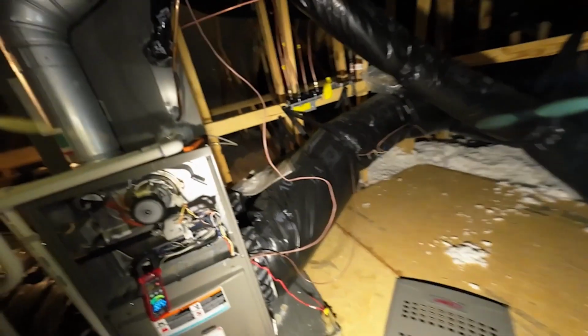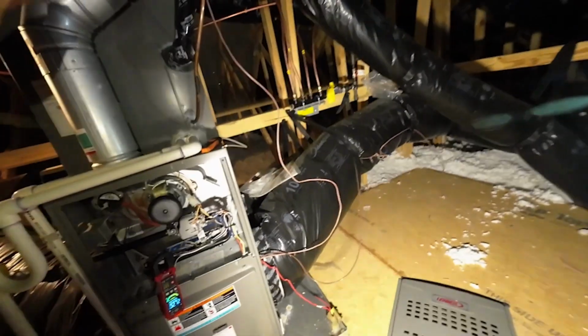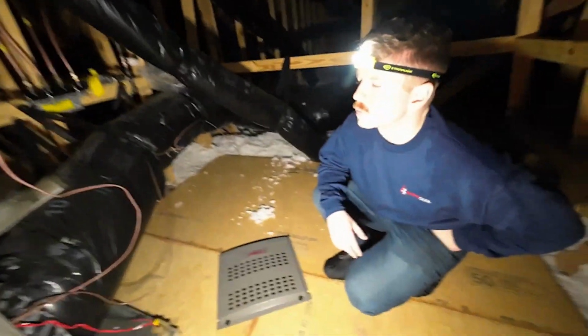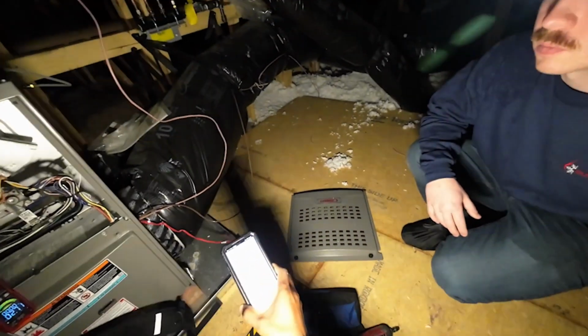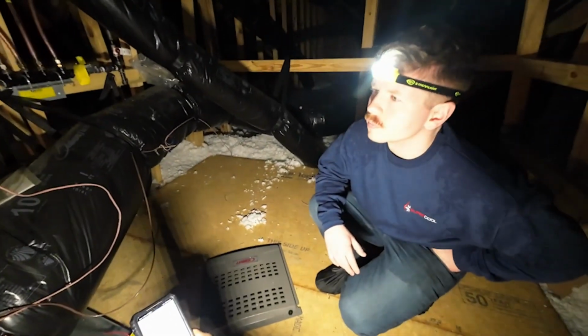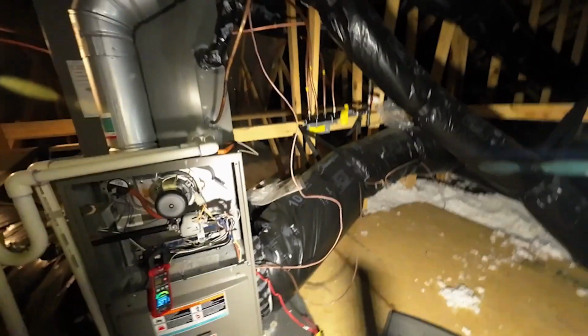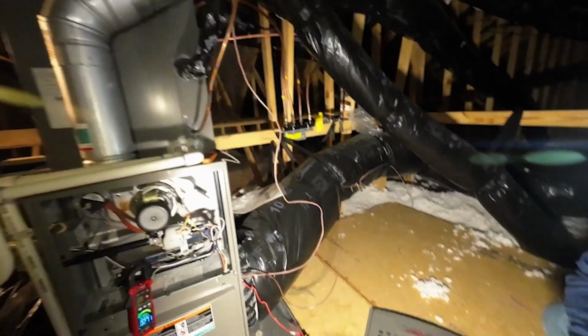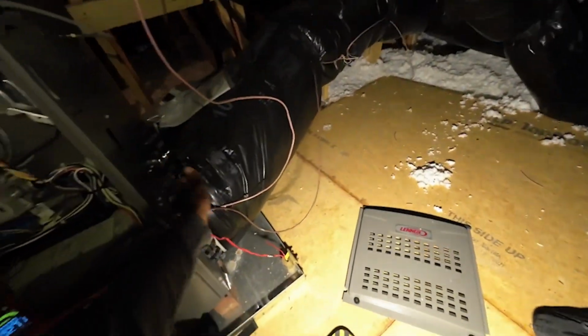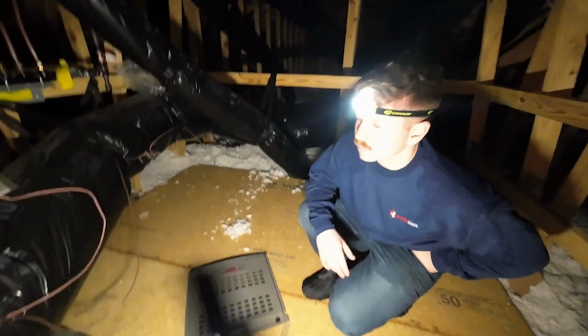So just imagine it like this. If I were to take this coil off and put a piece of wood on top of it, this static pressure would be off the charts. It would probably be like 2 inches of static pressure, okay? So that's just kind of like an extreme so you can get the idea of what's, and then if I were to take these off, and just put wood in front of that, then it would be the same. It would be 2 inches of negative static pressure. You see what I'm saying?